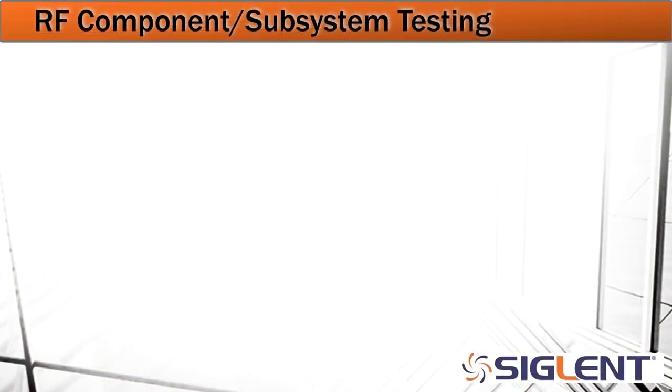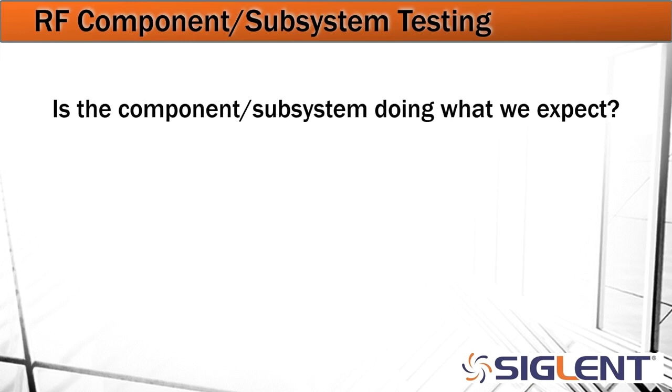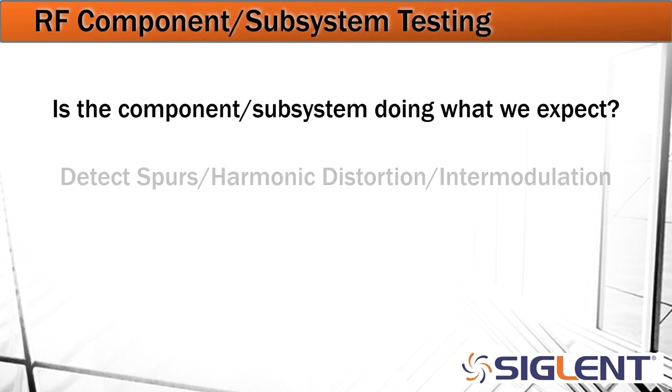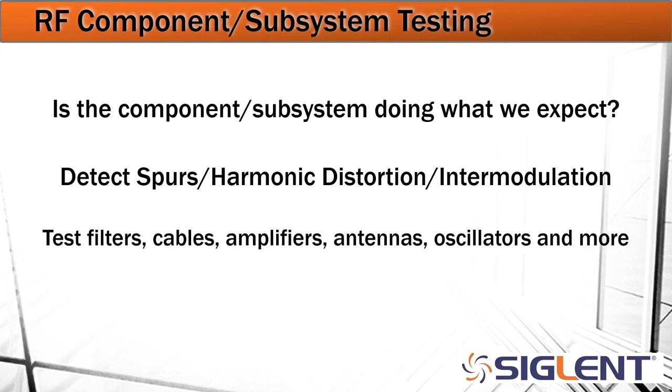The next application space I'd like to take a closer look at is going to be RF component and subsystem testing. Is the component or subsystem doing what we expect? If we expect it to be outputting an amplifier to output 10 dBm, is it actually going to do that with the given input? And is that going to work over a particular frequency range? Or is our filter working correctly? We can detect spurs, harmonic distortion, and intermodulation because the spectrum analyzer is going to allow us to visually see exactly what's happening with respect to frequency in that particular component or subsystem. And finally, we can test filters, cables, amplifiers, antennas, crystal oscillators, and more because again we can visually see the frequency ranges and the actual frequency footprint and amplitude directly on the spectrum analyzer display.